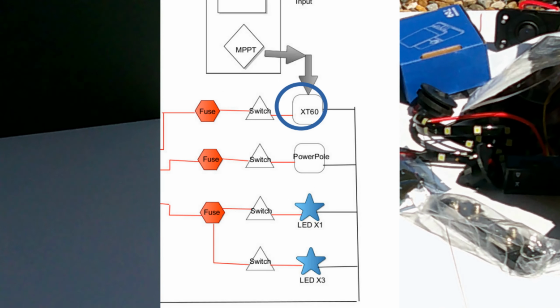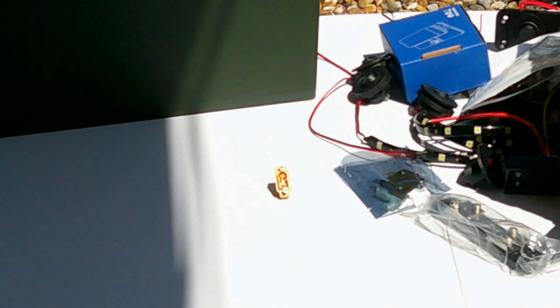I meant to point out earlier—this little yellow item is an XT60 connector that will be mounted, a panel mount connector. The battery is 20 amp hour, so you're not going to drain a whole bunch of amperage out of it, hopefully. Coming off the positive and negative terminals will be 10 gauge wire, and the positive again will go through a circuit breaker, onto a switch, and into the load center power distribution block. Up to that point, I want to use 10 gauge wire.